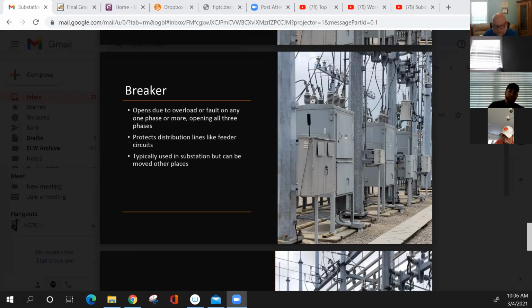It actually does have settings inside of it, and we'll go into that in power systems. We'll talk about breaker operations more, but it operates to try to clear a fault before it actually locks itself out. It really depends on the engineer who set up these breakers in the sub as to how many times they operate. But I know in the Duke system, if a limb falls across these phases out in the field and that breaker operates, it has what it calls a quick trip, or instantaneous trip. It'll trip very fast, like less than a second. It trips and comes right back on.